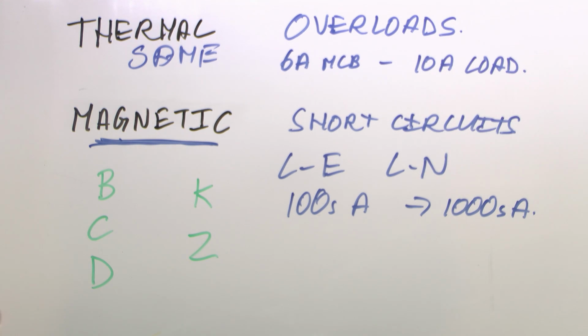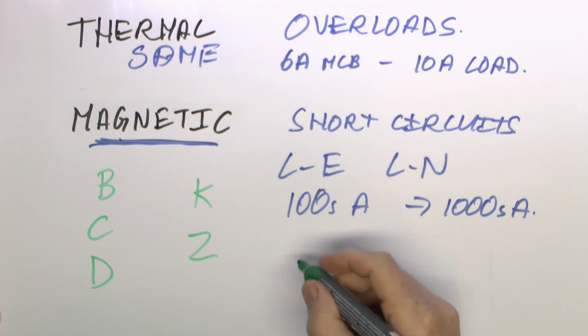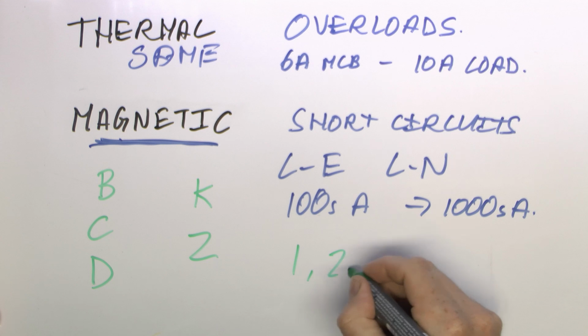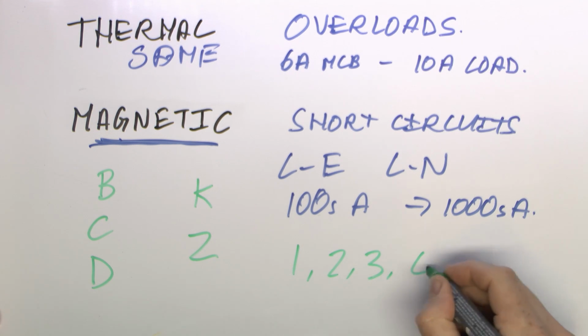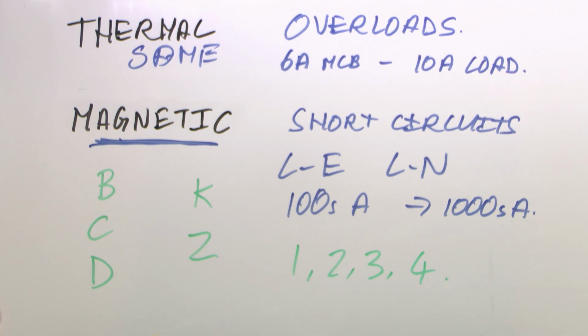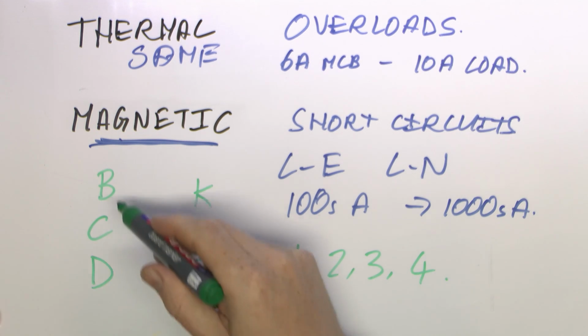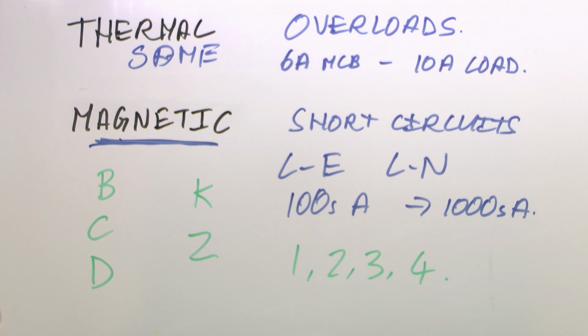Now, before B, C and D came along, there was another system of defining what types these were, and that system actually was a number system. It was 1, 2, 3 or 4. Now, this hasn't been used for quite a number of years, but of course there's still lots of circuit breakers out there installed which will have this on the front, and these typically will say things like type 1, type 2 or whatever, rather than just having the letter in front of the rating. So not something you're going to actually be installing, but you will find them in older installations.